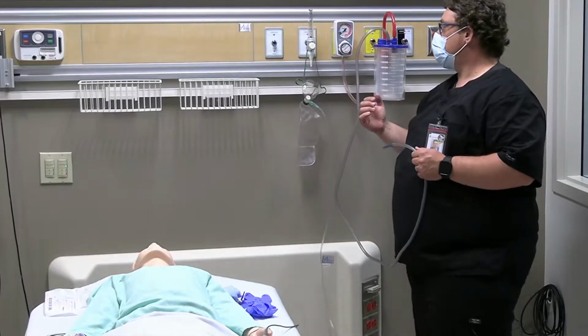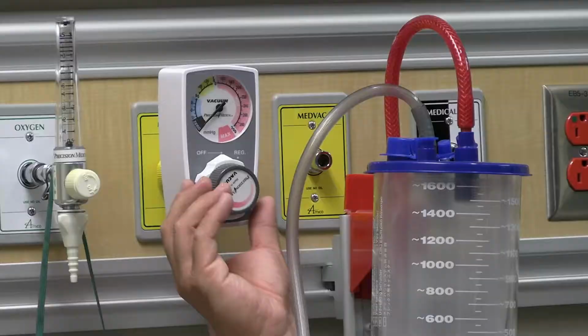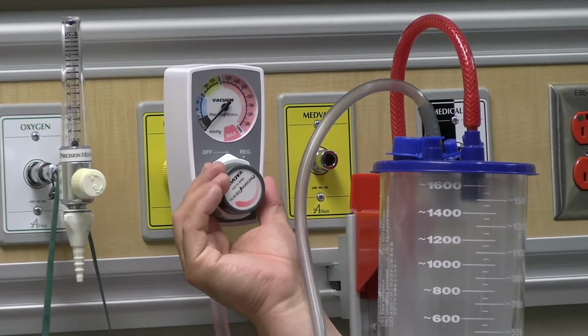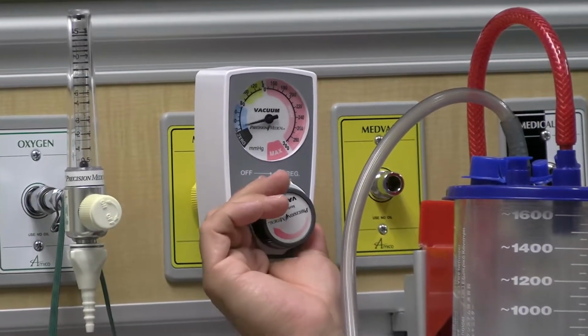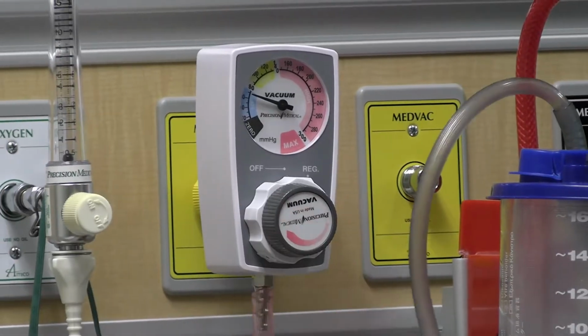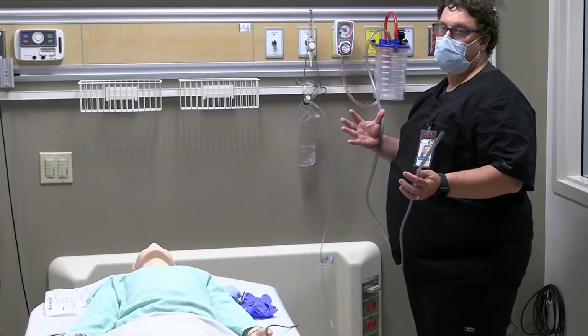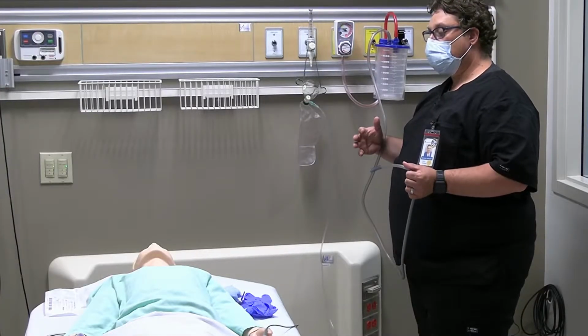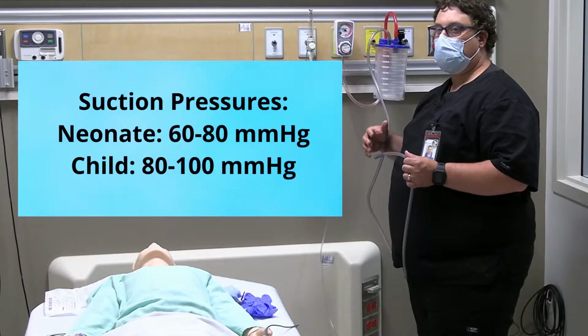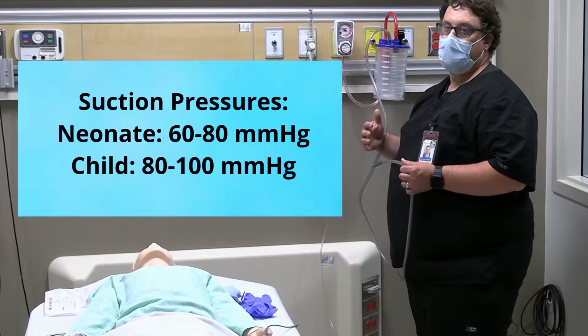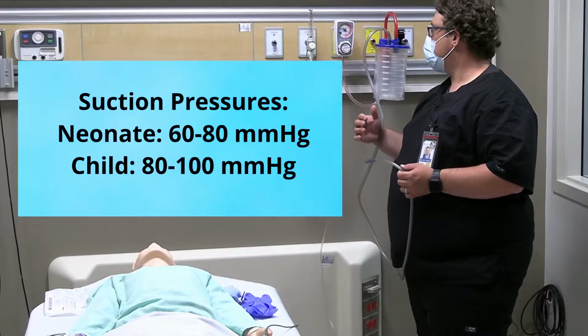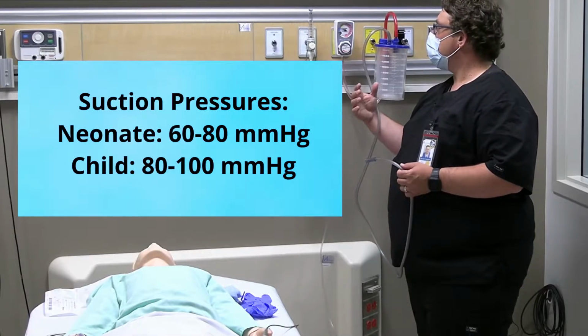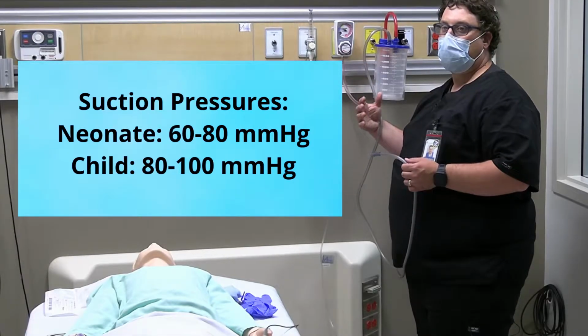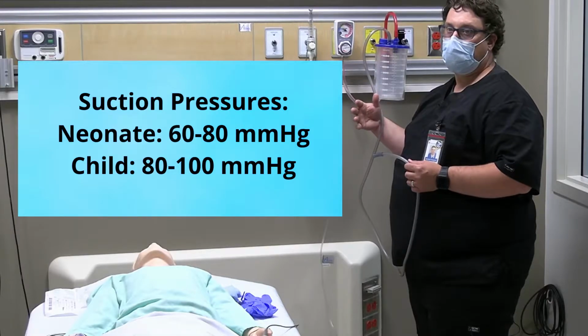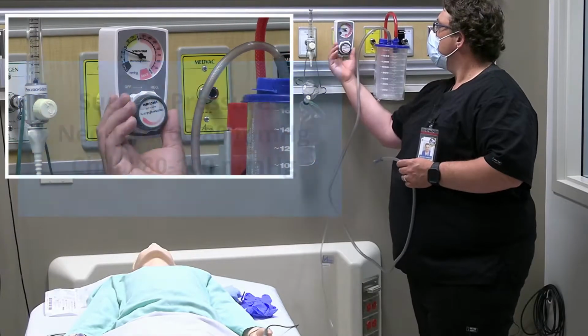In terms of setting your suction regulator, you want to make sure that your suction is set to reg or always on. And then you want to adjust your pressures depending on the size of your child. If it's a neonate, we typically recommend ranges of -60 to -80 millimeters of mercury of suctioning. The older the child gets, probably anywhere between -80 and -100 millimeters of mercury for suction.